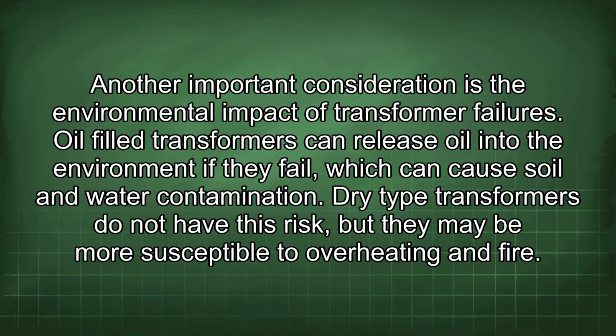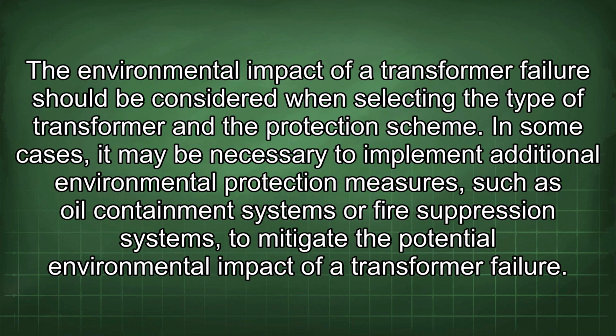Another important consideration is the environmental impact of transformer failures. Oil-filled transformers can release oil into the environment if they fail, which can cause soil and water contamination. Dry-type transformers do not have this risk, but they may be more susceptible to overheating and fire. The environmental impact of a transformer failure should be considered when selecting the type of transformer and the protection scheme. In some cases, it may be necessary to implement additional environmental protection measures, such as oil containment systems or fire suppression systems, to mitigate the potential environmental impact of a transformer failure.